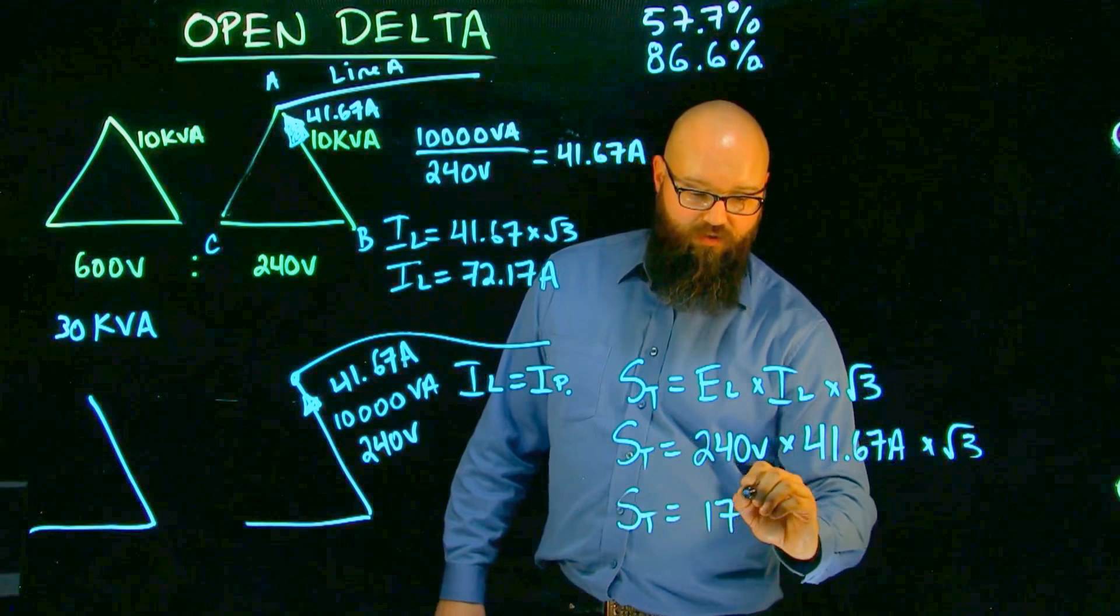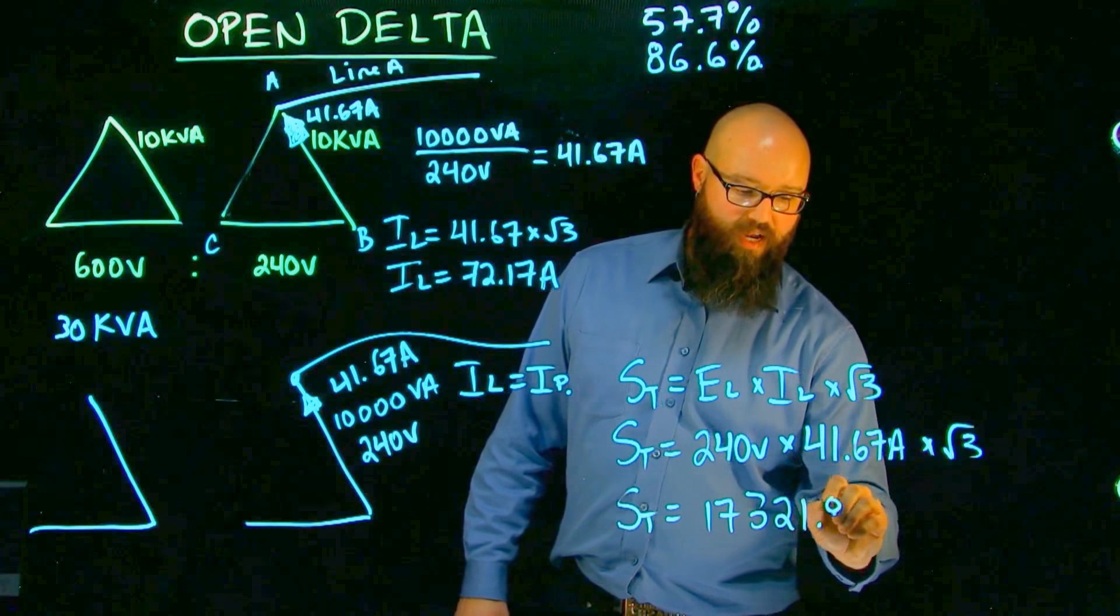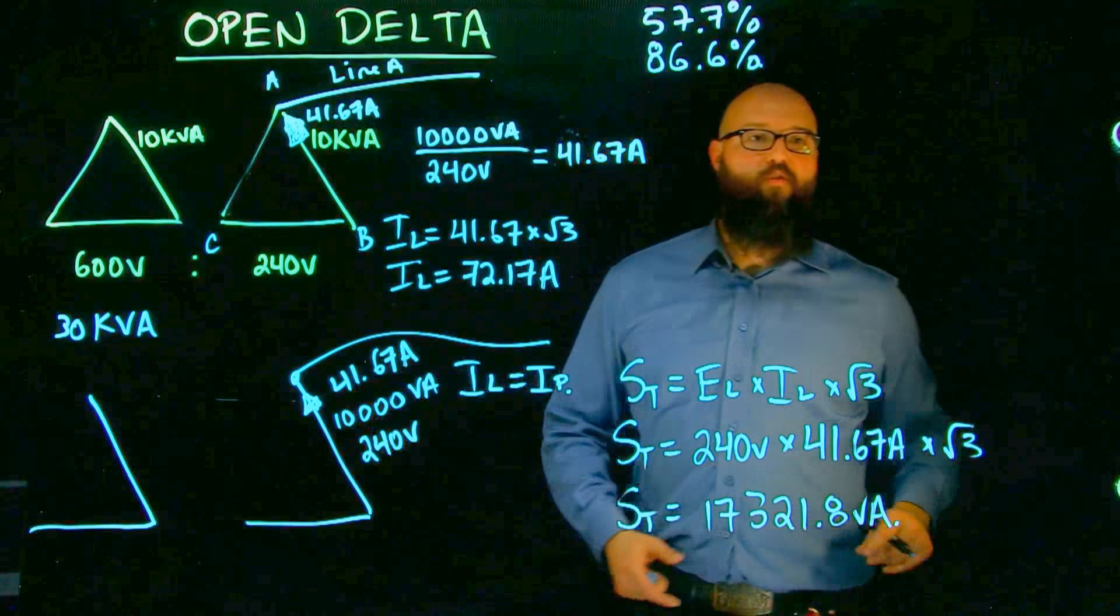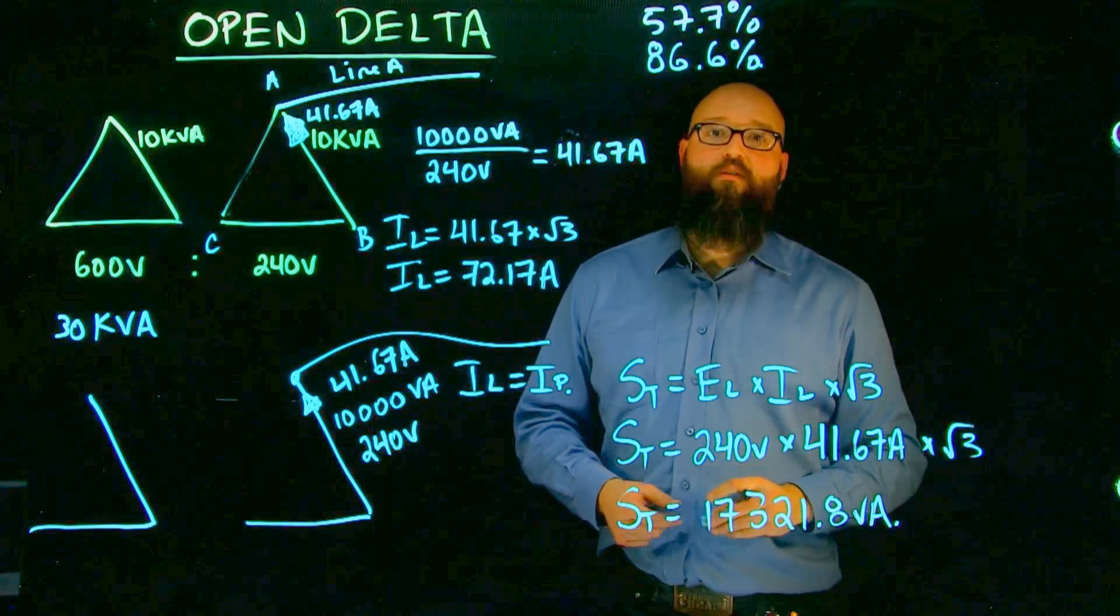times now our line current of 41.67 amps times root three, we end up with an S total now of about 17,321.8 VA. That is now the output of this transformer with its rated current.